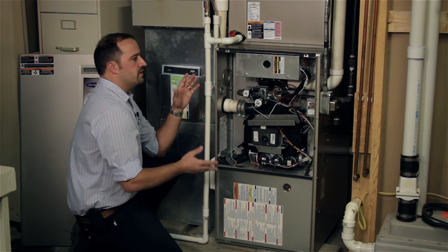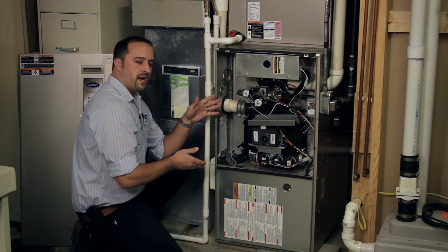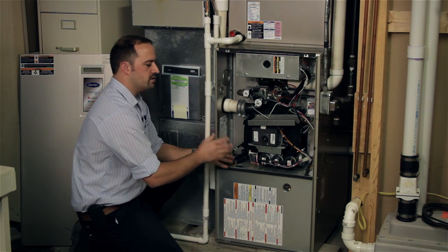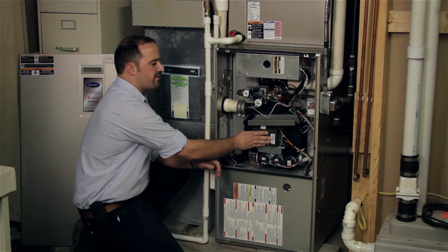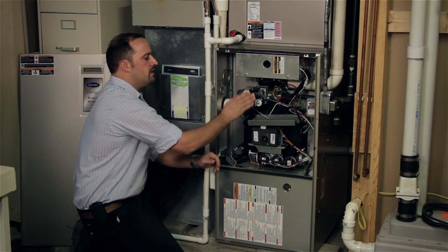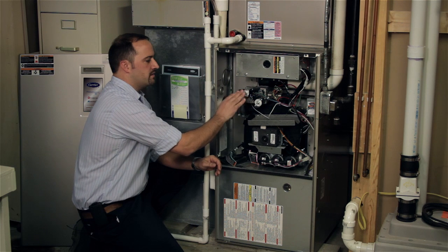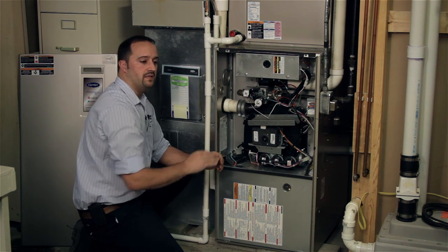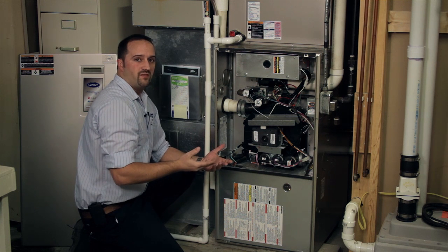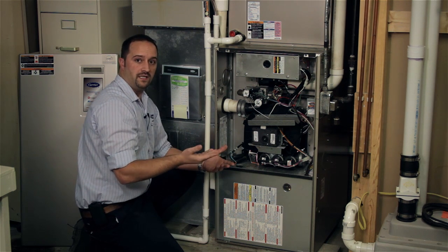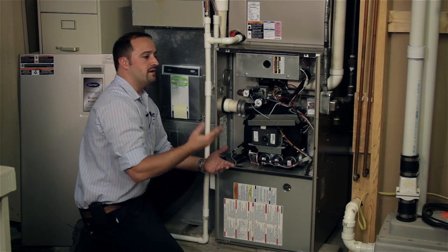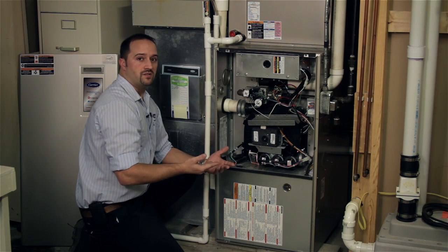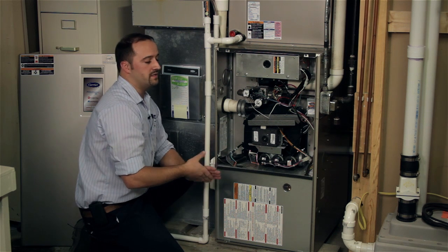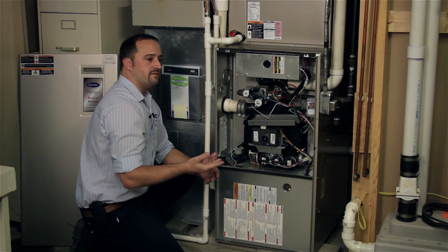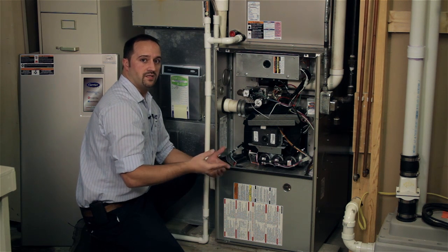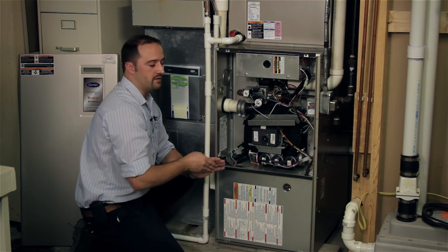So after the technician goes through and checks the heat exchanger and has verified that there's no cracks in it or any issues with it, he's going to go ahead and check the bearings of both the blower motor and the draft motor. He'll check the burners. He'll go ahead and put his special tools on to measure the gas pressure that's coming in. Your furnace burns at a certain amount of pressure. If there's too much pressure, it's going to overheat or cause undue stress on the heat exchanger. If there's too little gas pressure, it can actually start sooting up and also cause issues with the heat exchanger. So he's going to make sure that's dialed in. Every manufacturer has a different gas pressure setting, so he's going to make sure it's at the optimum pressure setting for your furnace.